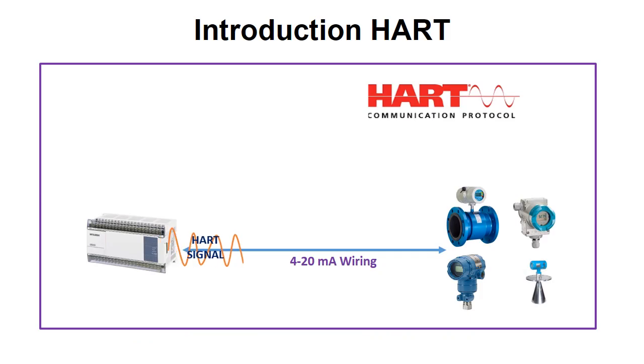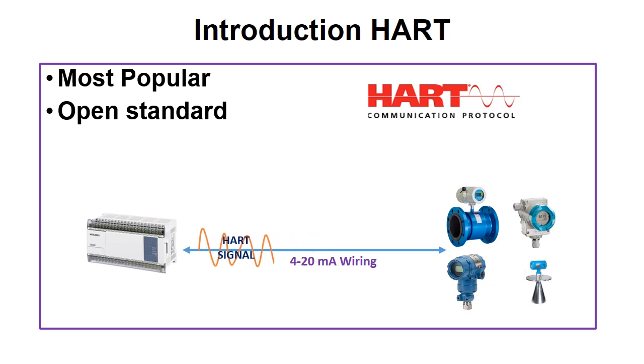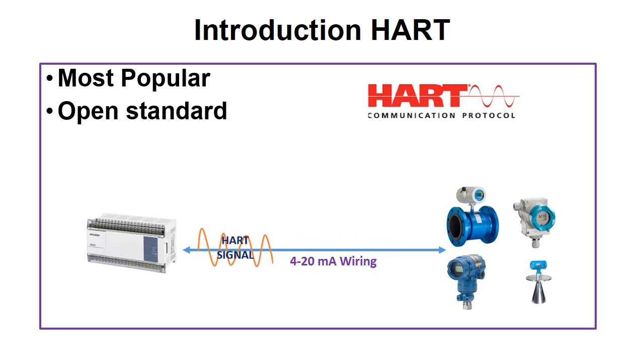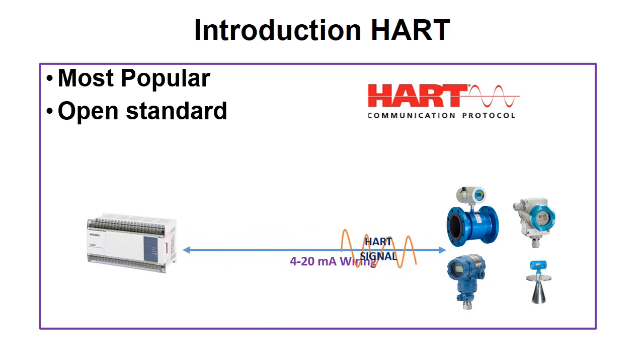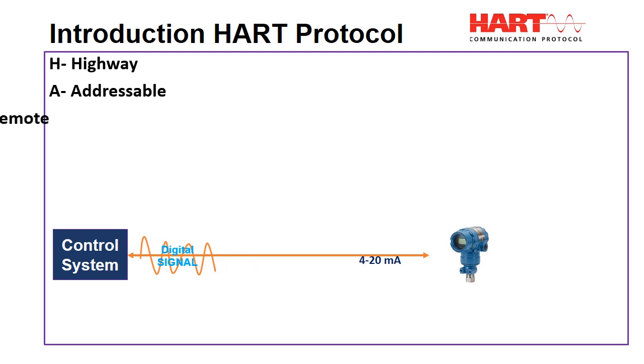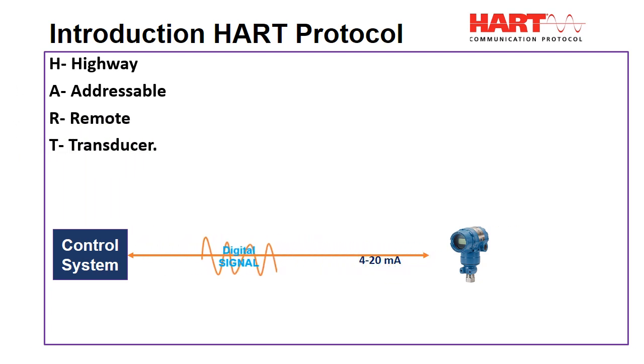HART is the most popular open standard communication protocol in the instrumentation and automation industry. HART is globally used to send and receive digital data using analog wiring between control systems and smart field devices like pressure, flow, level, or temperature transmitters, valve positioners, actuators, and many more. HART stands for Highway Addressable Remote Transducer.